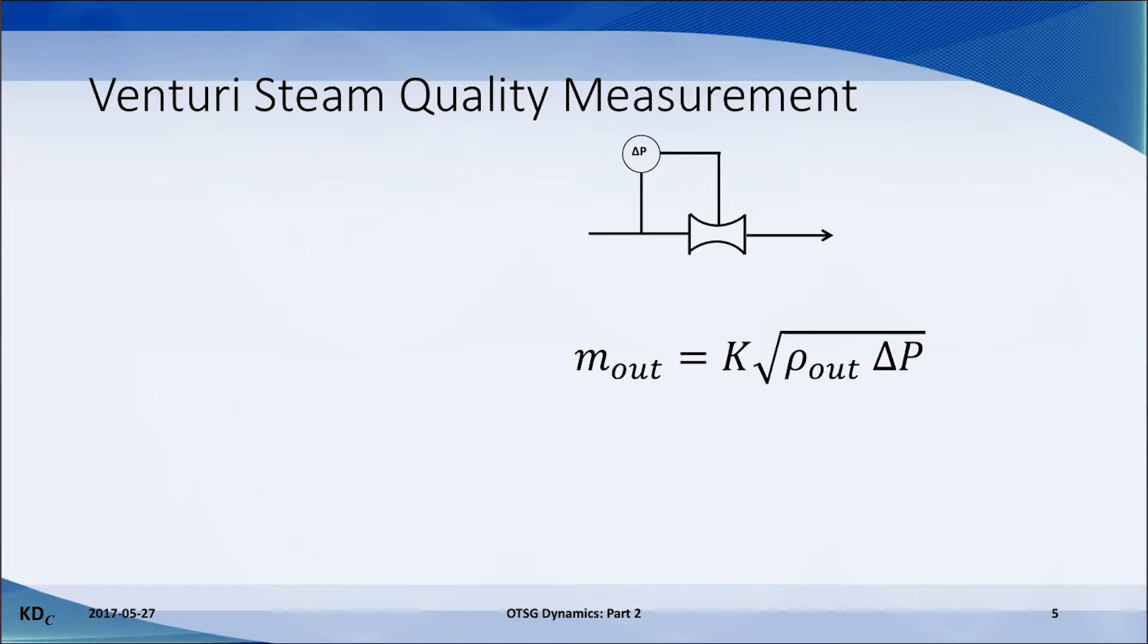Let's start with a standard venturi that is used to measure a flow rate. We measure the pressure drop across the venturi, we know the fluid density, and we are given the meter constant for the venturi. Then we use the venturi equation and we determine the flow rate.